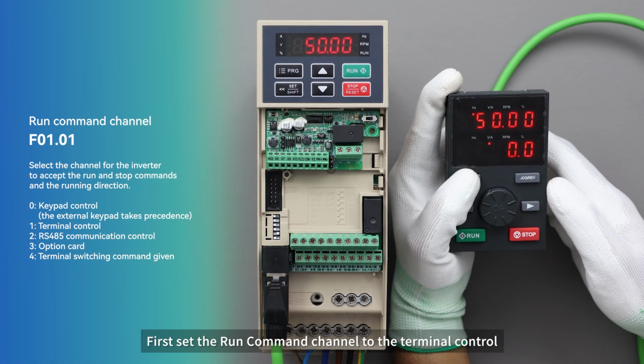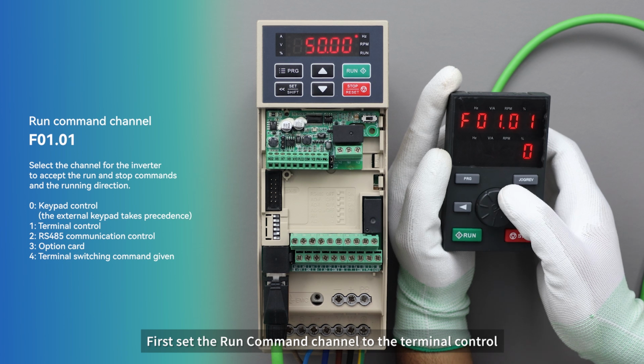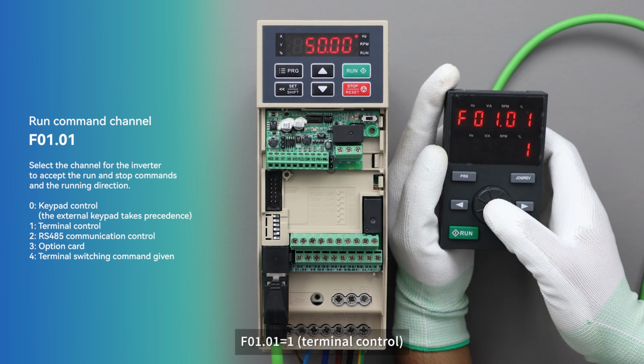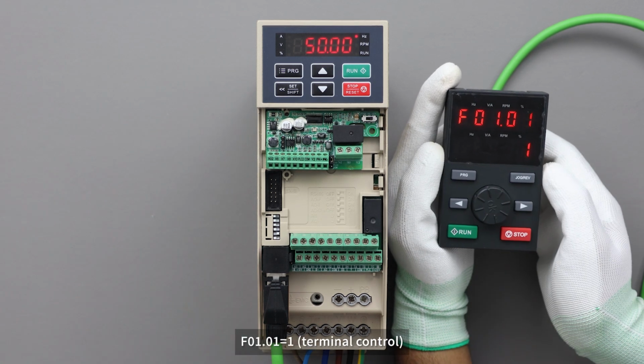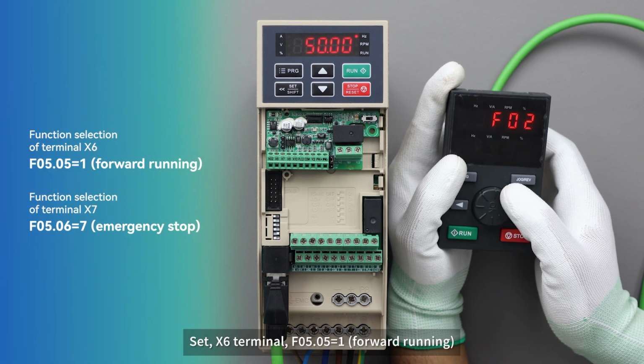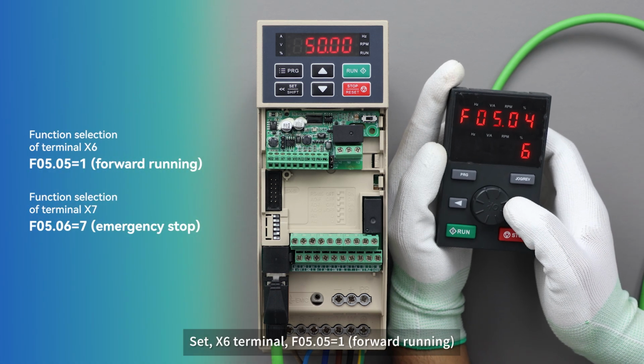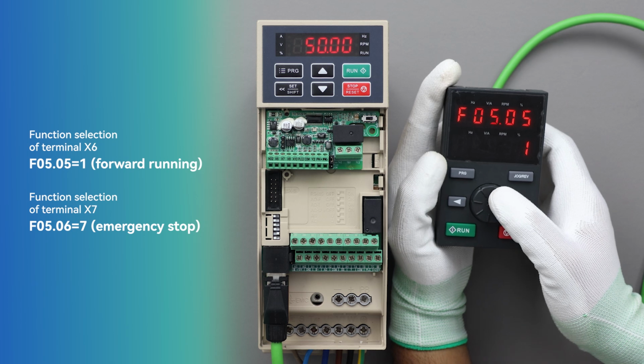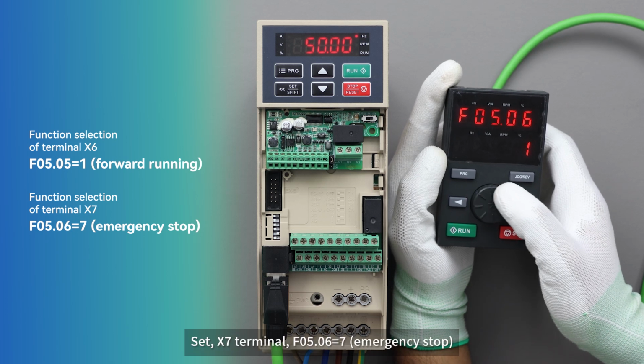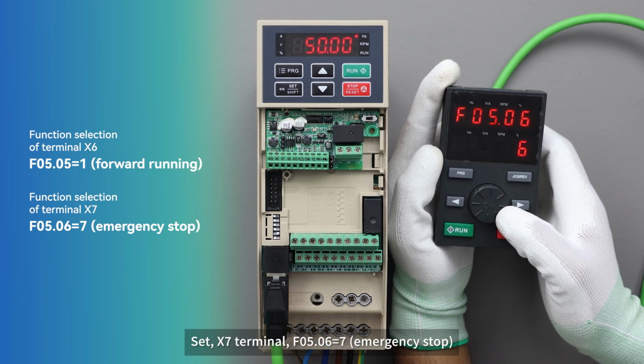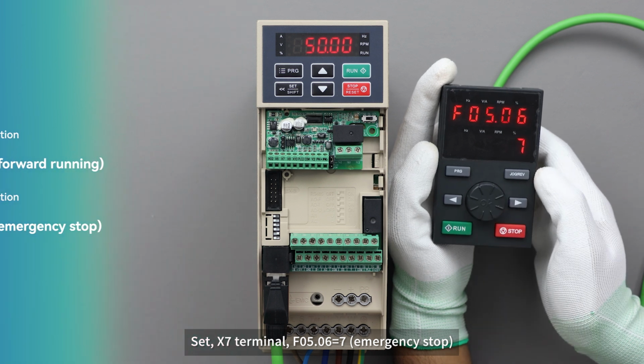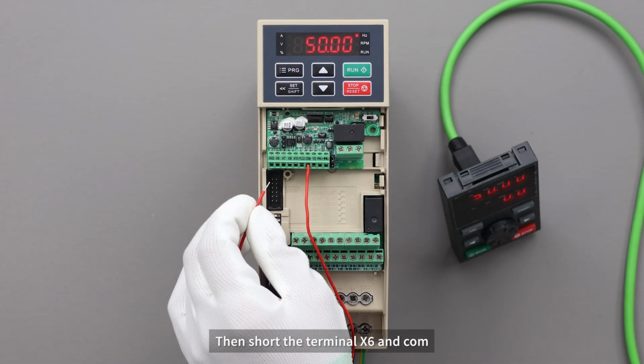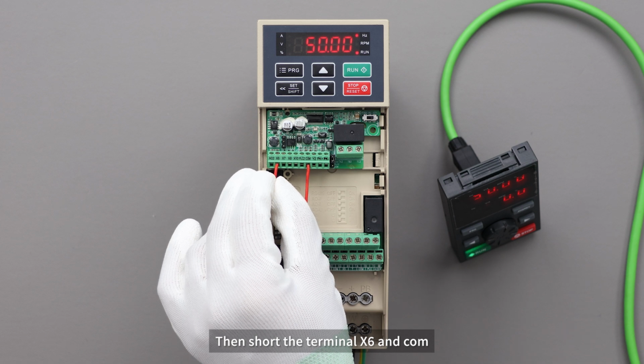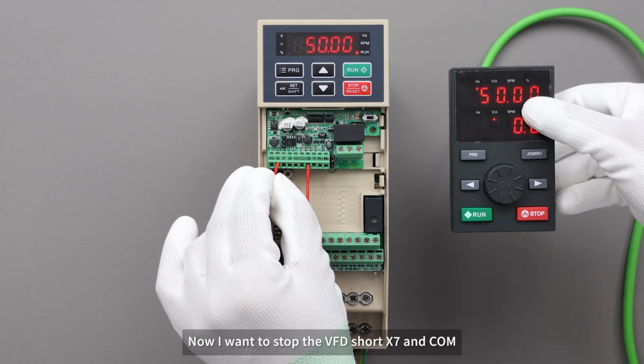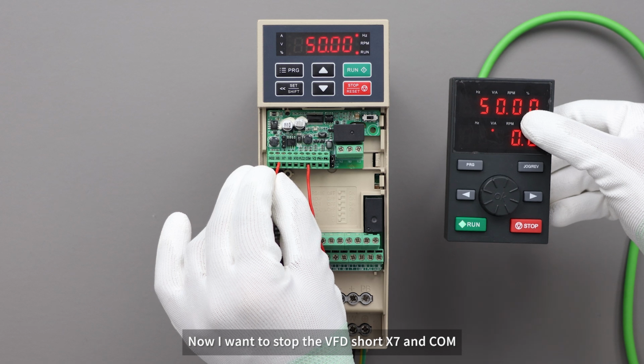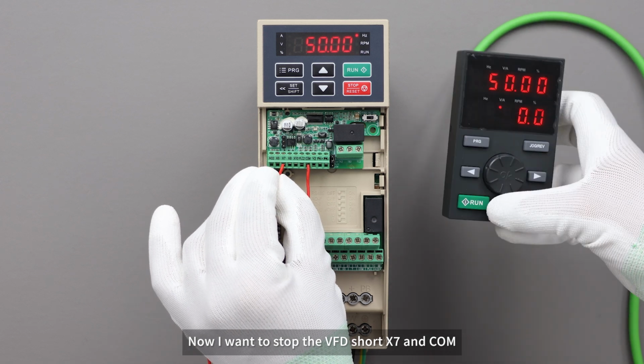First, set the run command channel to the terminal control. F01.01 set 1. Set X6 terminal F05.05 to 1. Set X7 terminal F05.06 to 7. Then short the terminal X6 and COM. Now I want to stop the VFD, short X7 and COM.